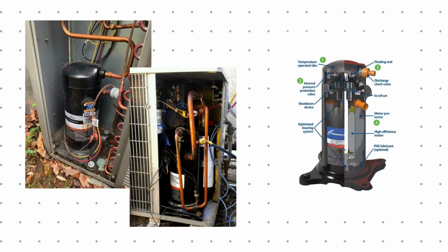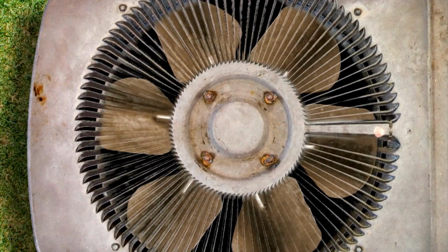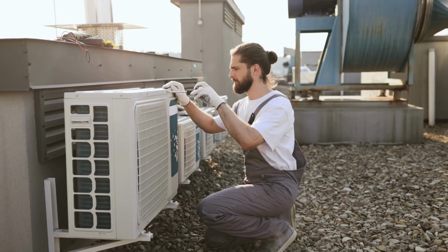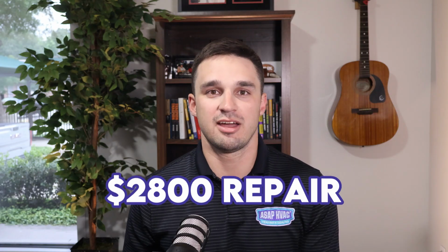Protecting your compressor. Now let's talk about protecting what's most often the most expensive component in your system, the compressor. When static pressure isn't right, it messes with the airflow over your evaporator coil. This can cause liquid refrigerant to flow back to your compressor, and compressors are designed to pump gas only, not liquid. This is what we call flood back in the industry, and it's absolutely devastating to your compressor. It can damage the internal scrolls, throw off the compression ratio, and lead to inefficient operation. Eventually, it'll cause the complete compressor to fail. We recently replaced a compressor that had failed after just 4 years, and due to high static pressure issues, that was a $2,800 repair that could have been prevented with proper static pressure management.